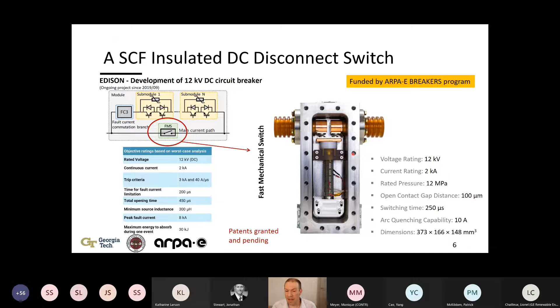It is possible. The key element that plays a very important role is that the high density of the medium allows for excellent heat transfer, good arc cooling capabilities, but also high dielectric strength, which in combination should allow us to actually shrink the volume of gas. That is the key here, that we can reduce the diameter of the chamber of the breaker, so that we don't end up with extremely high wall thicknesses. What you've seen is a photograph of the disconnect switch. This is a wall thickness of about 3 centimeters, 30 millimeters, of a high-strength steel alloy. This is in part because it's a boxy shape. As soon as you go towards a more round design, something based on a pipe, you can further reduce the wall thickness.